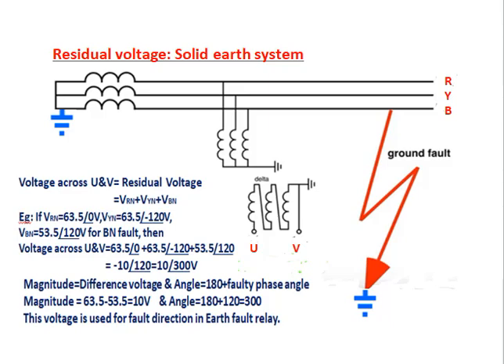Residual voltage in a solid earth system: the transformer neutral is directly connected to the star point, a PT is series-connected, and UV is an open delta voltage. If a BN fault occurs, the BN voltage is reduced. The residual voltage across U and V equals Vrn + Vyn + Vbn. For example, if Vrn = 63.5∠0°V, Vyn = 63.5∠−120°V, Vbn = 53.5∠120°V, then residual voltage = 63.5∠0° + 63.5∠−120° + 53.5∠120° = 10∠300°V.